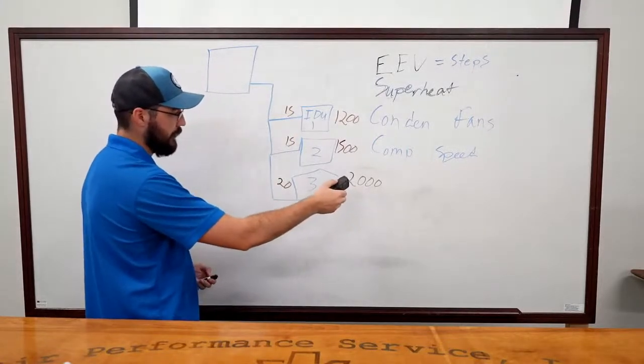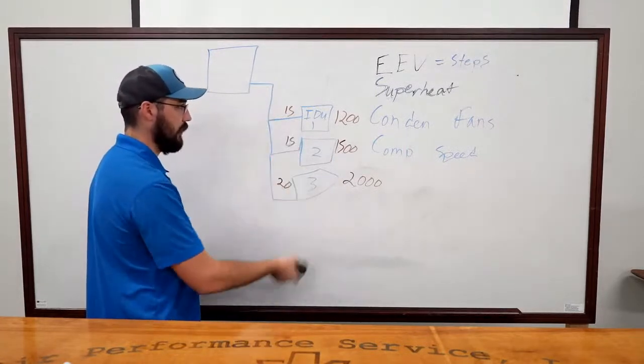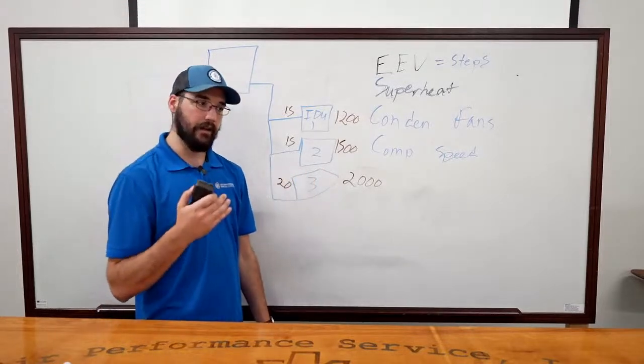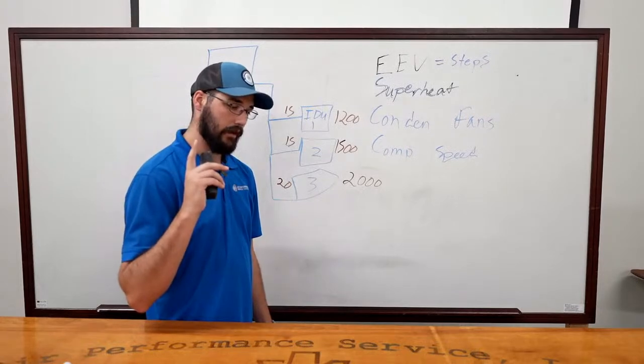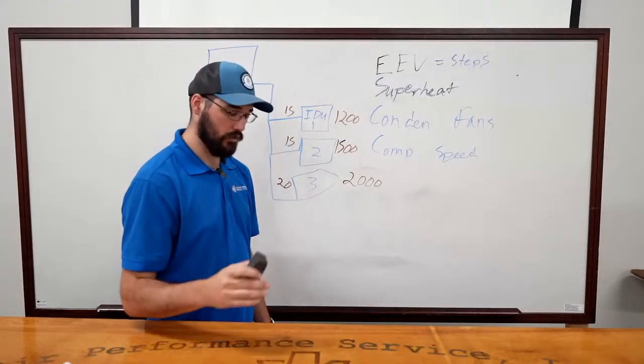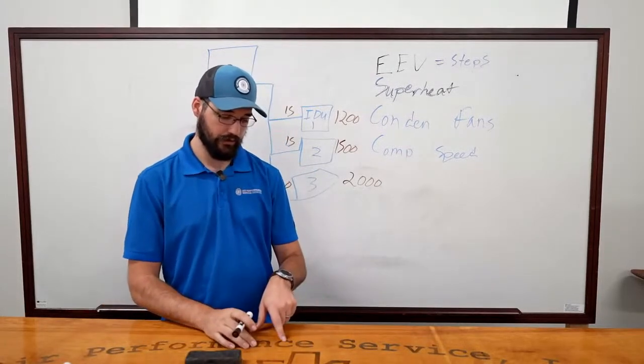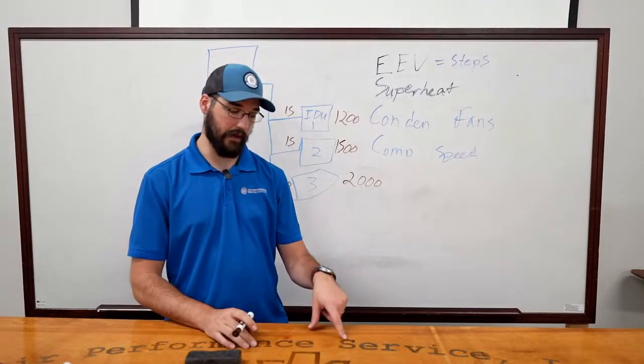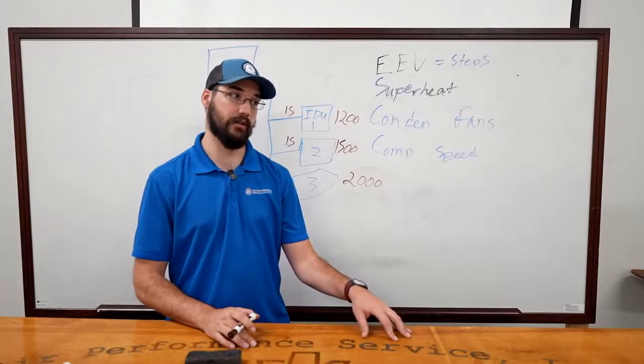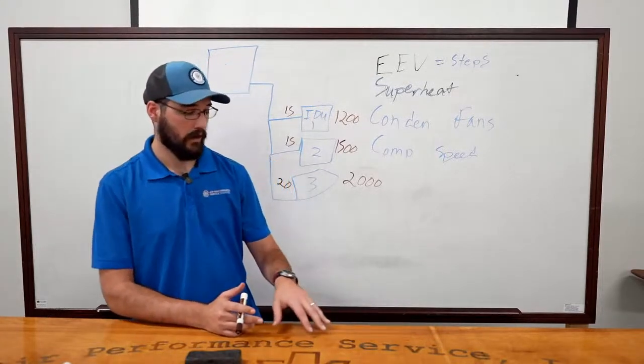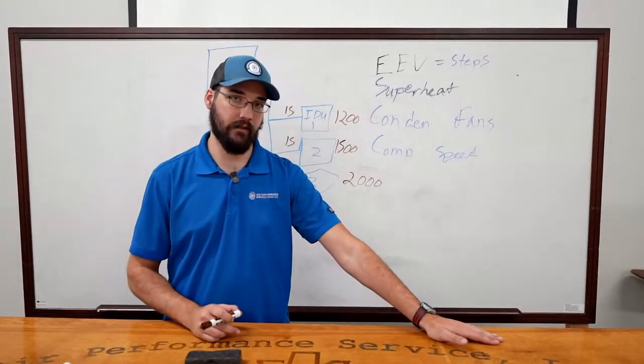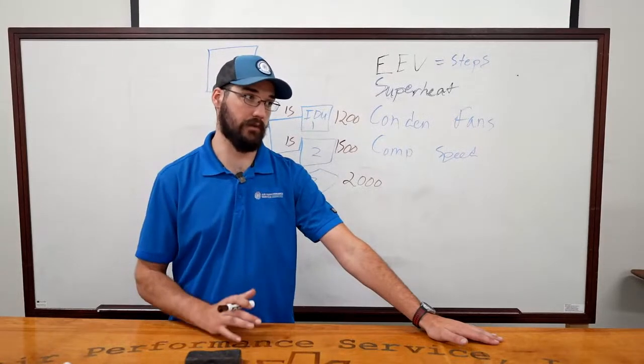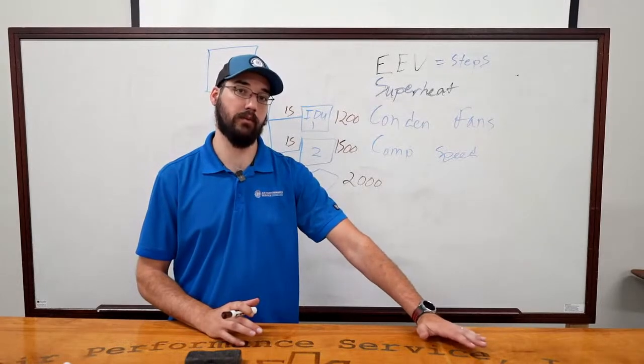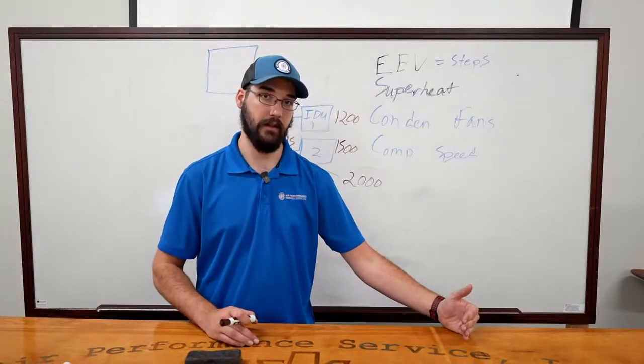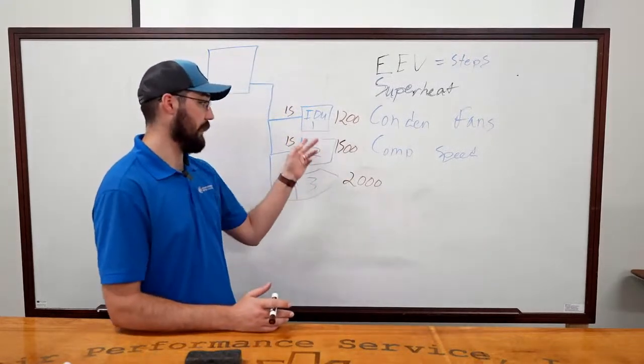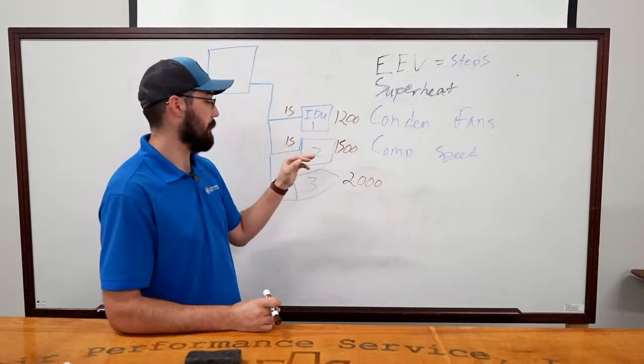So this would be, on a very simplified level, a low charge. We can do a temporary charge. If you run into this, my personal rule of thumb is, if we lose as much as 40% of that refrigerant charge, and it's a blend, so being 410A most of the time, we can't leave that in there, and I don't want us to leave that in there. For our team's level and perspective, we need to push the customer to go back with virgin charge completely. Now, it doesn't mean the temporary, because if this is the case, we've got a significant leak. We need to find and fix that leak. We'll talk about that more in a second.